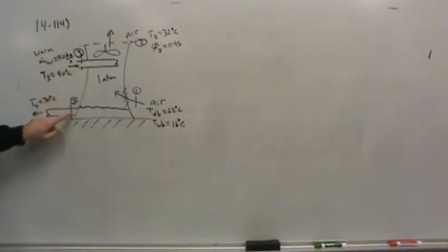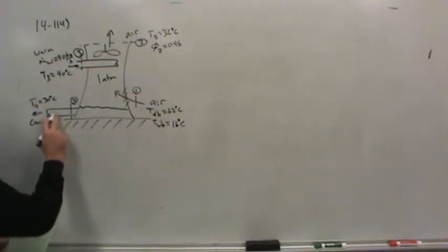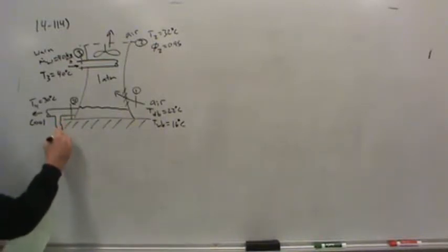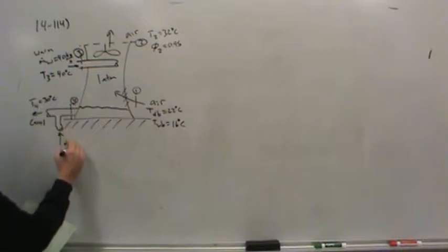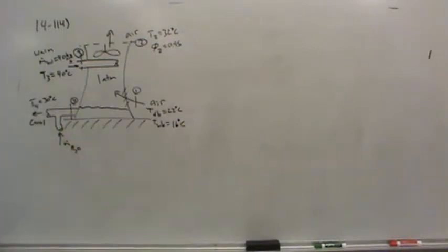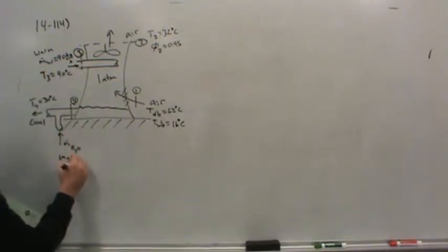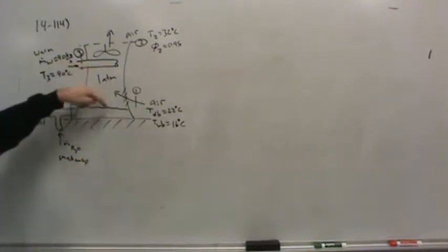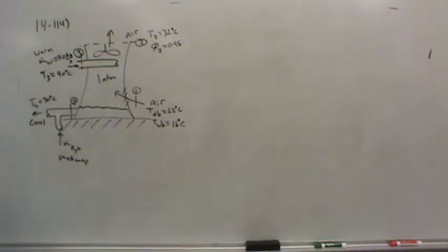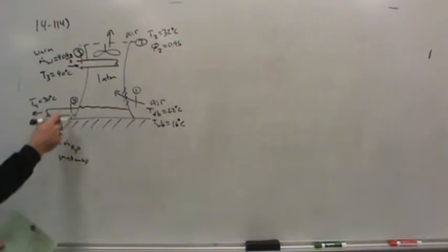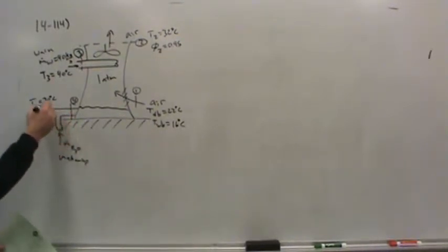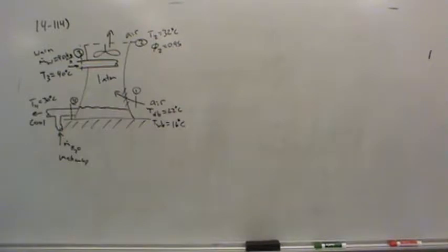Now, since we need 40 kilograms per second to go back to the process and cool probably a condenser and a power generation unit, well, then we're going to have to provide some makeup water. Okay, so there will be some makeup water, and that flow rate, I gave the symbol m.H2O. Okay, both of these are flow rates of water, but this is makeup water. And the reason we need it is because some of the water that comes in evaporates off and goes out into the atmosphere. We've lost it. Now notice that I was careful where I chose state 4. I did not choose state 4 cutting both of these lines. You'll see why in just a minute in the equations.